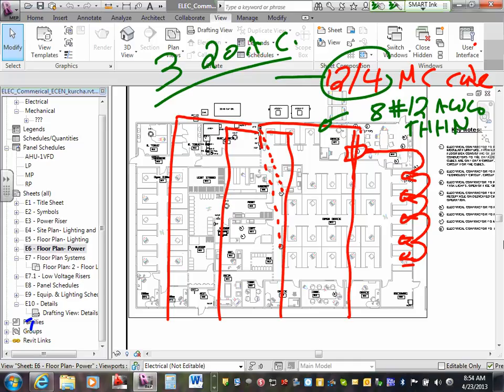Cool? All I'm saying is why don't we do it according to what you're going to see most commonly out in the field? That's all I'm saying. Do it. I don't like the word most commonly, but you do it. The best design, the best installation, is if you do not pull a multi-wire branch circuit. I'm not going to argue with this, because from a maintenance point of view, you build the building for 50 years to come. For people like yourself who are going to be maintaining the building. So if you want to use a multi-wire branch circuit, then you have to have either a special cable, or you're going to be using multiple 12-2.